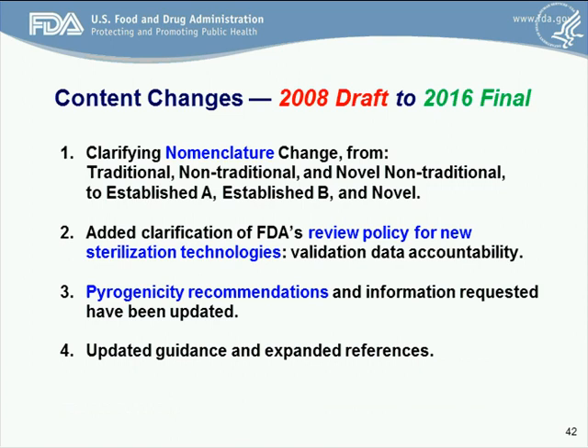This slide summarizes all the content changes from 2008 to 2016. This includes a nomenclature change — the previous version included traditional, nontraditional, and novel nontraditional methods; now we're looking at established A, established B, and novel methods. Added clarification is provided of FDA's review policy for new sterilization technologies and validation data accountability — the key message. We want to know whether the validation data is sufficient because it conforms with existing standards or because we've already reviewed it, or we need to see new validation data for the first time. Pyrogenicity recommendations and information requested have been updated, and updated guidance and expanded references have been provided throughout.